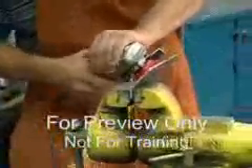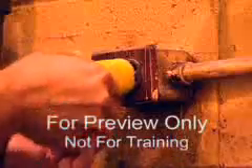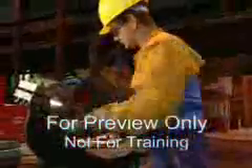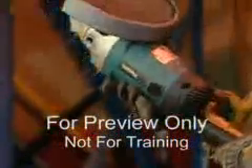To protect yourself and coworkers from electrical shock or burns, power tools have either a 3-wire cord with a grounding prong or are double insulated. Double insulated tools have an internal layer of protective insulation completely isolating the tool's external housing. To check if a tool is double insulated, look for the Underwriters Laboratories seal and a double insulation designation.